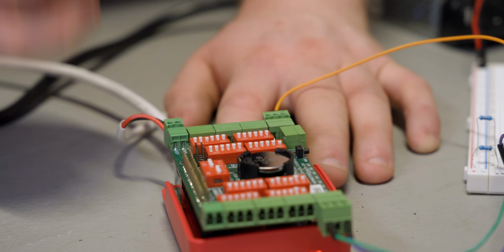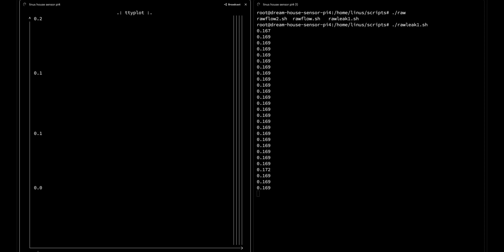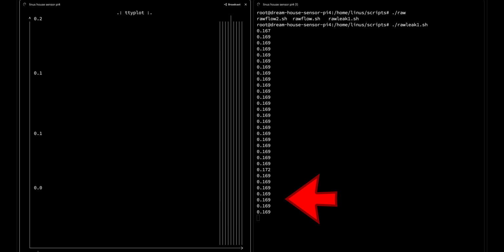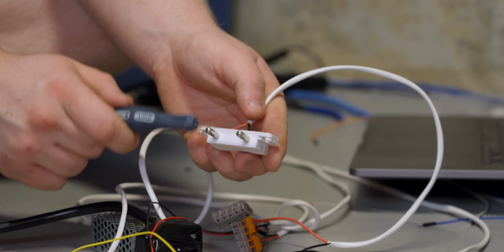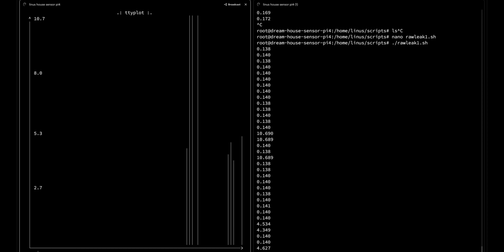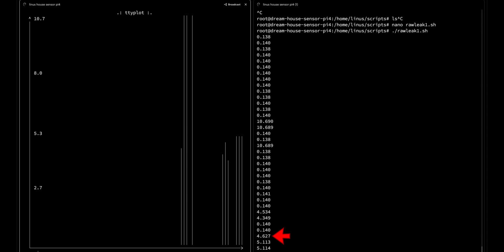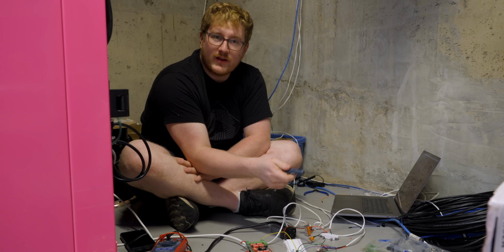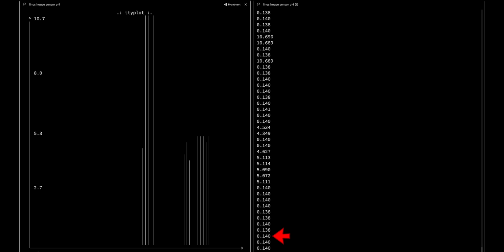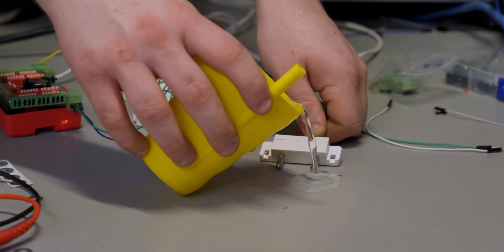The last thing we have to do is adjust the sensor on the board to be a 0 to 10 volt sensor. We can see it's reading about 0.17 volts when in theory nothing is connected. If I bridge this now with a screwdriver, which is metal, it goes from about 0.1 volts right up to 5, which makes sense. When I let go, there's no path, and it reads 0.14. Now we just need to try it with some water.